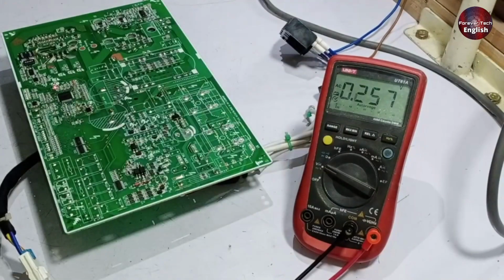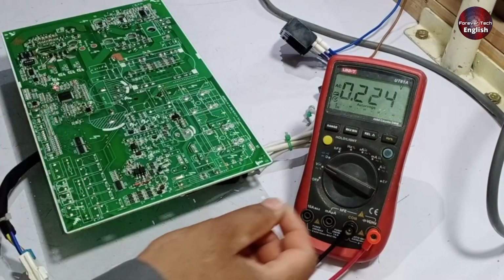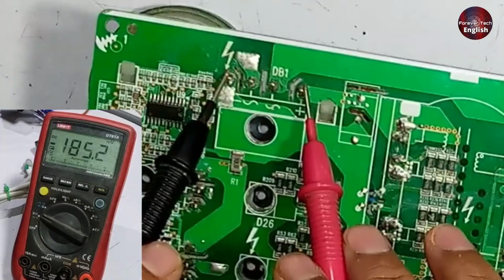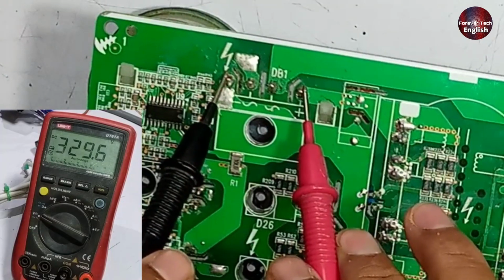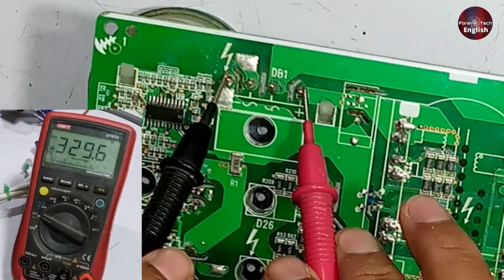Next, the points beyond this need to be checked in DC mode, so set your multimeter to DC volts. After rectification, you should get 320 volts. Here, we are reading 329 volts, which is correct.